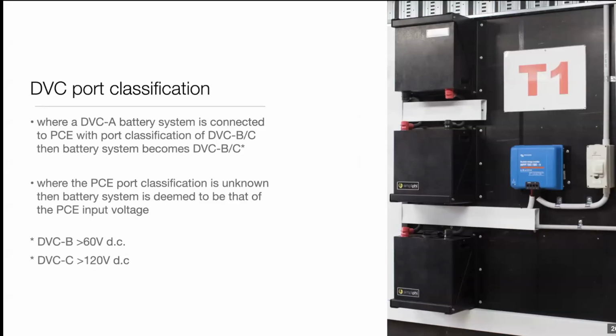Port classifications. Now, there's an example in this picture of a Victron MPPT, and that Victron MPPT can take up to 150 volts on its PV array port, but it's connected in this case to a 48 volt SimpliPhi lithium-ion battery system. Now, because of the port classification, the port meaning the connection of an energy source or communication, if there is no galvanic isolation between ports, then the highest voltage present deems the classification of all of those ports. So you might have a PV array that's operating at, let's say, 100 volts, but a battery system that never goes above 50-something volts.